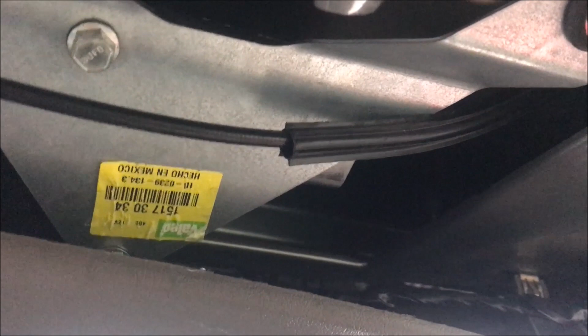And then when the switch is turned on, the gray with your red probe and the other probe on the ground should show battery voltage. And then if you go to that plug and put your black probe to the ground wire and your red probe to the red wire, it should show battery voltage, but you'll probably have something less, 4.2 or so is what I had. And then in this case, we came over here, pulled this connection apart, found those two wires that I jumped past the burned out connection, and now everything works.